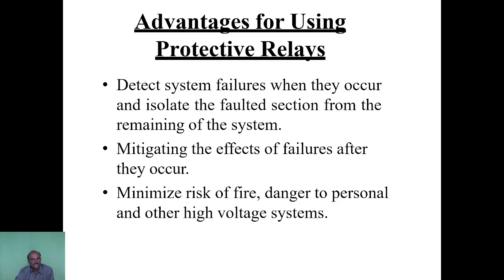with logic functions. Advantages of using protective relays. What are the advantages? It detects system failures when they occur and isolates the fault section, mitigating the effects of failures after they occur. So not only does it identify the fault, it is also involved in mitigating the failures, and it minimizes the risk of fire and damage to personnel and other high voltage systems.